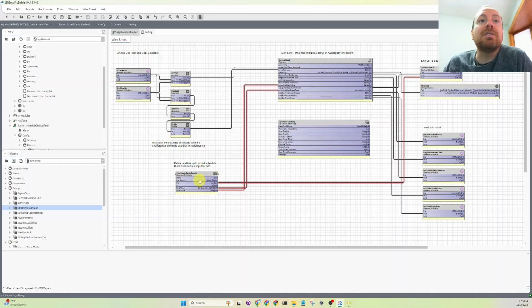That's the whole point of these blocks: they need to know the schedule to operate the HVAC, like the next value and the next time. Because if we're unoccupied and the building is going to be occupied in 2 hours, that's our critical time, and we want to calculate how soon we'll be able to recover the zone temp to set point.